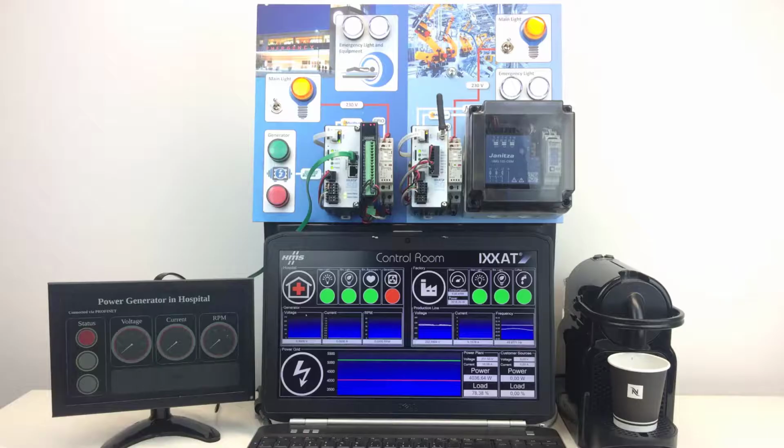The production consumption is measured by an electric meter that is connected via MODBUS, and the electric power is analyzed by a Janitza module connected via MODBUS. The SG gateway bridges the gap between these devices, which are running on different protocols, and the SCADA simulation running on 61850.